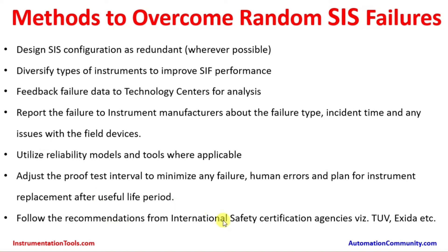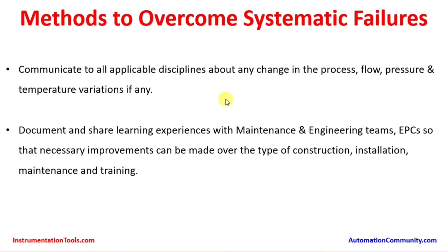It is important to follow recommendations from international safety certification agencies like TÜV and EXIDA. These agencies perform detailed analysis for each instrument manufactured and supplied to plants at different environmental and geographical conditions, subjecting instruments to rigorous testing before certifying them for service. End users and manufacturing companies should always go for certified products. Additionally, all applicable disciplines must be informed about any changes in process conditions such as flow, pressure, or temperature variations, as process changes can impact installed instruments — for example, a sudden pressure increase could cause a sensor to fail.